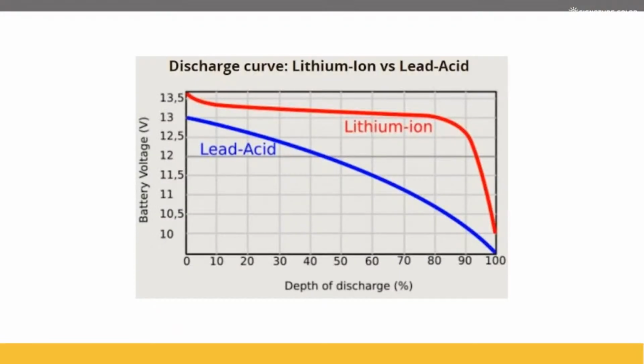So, state of charge. How do you teach the BMS where the battery is? You teach the BMS basically by just using the battery. There are certain ways to teach it what 0 is and what 100 is, and that's where you need to get a cell undervolted or overvolted, and then it will teach the battery what percentage it's at. But basically you do it through use. You use it down and then charge it back up to the appropriate voltage, and over time it learns what its range is and what state of charge it should be at.